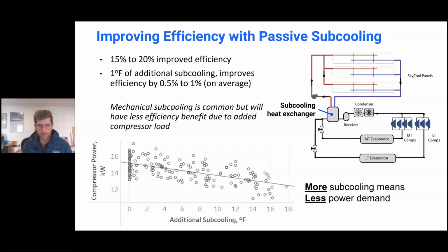As a general rule of thumb, for every degree Fahrenheit of subcooling that you can provide, you're going to add 0.5 to 1% efficiency to the refrigeration cycle, and the variance is really driven by the refrigerant type and the evaporator temperature, the suction pressure for the system. But you can see here some general data that we've been collecting. It is somewhat noisy, but this is from a refrigeration system where we've been able to add subcooling, and we isolated the data to show that the power essentially reduced as we added more subcooling in to the system.